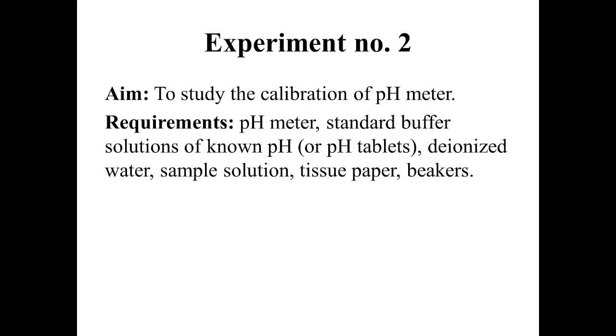Now, why do we need to calibrate a pH meter? So this is going to be your second experiment. The first experiment has been discussed by Dubey madam. So now what is our experiment? To study the calibration of a pH meter. What are the requirements? A pH meter, of course, which needs to be calibrated. Then a standard buffer solution having known pH, or pH tablets to be dissolved in buffer, which will have a standard, known pH. Then we require deionized water. We need the sample whose pH is to be determined. Then tissue papers, beakers, etc.